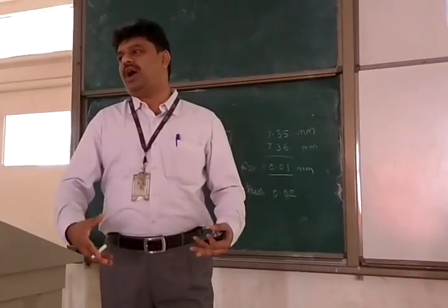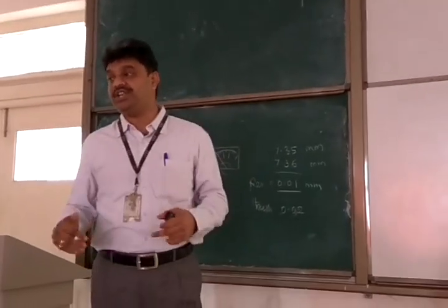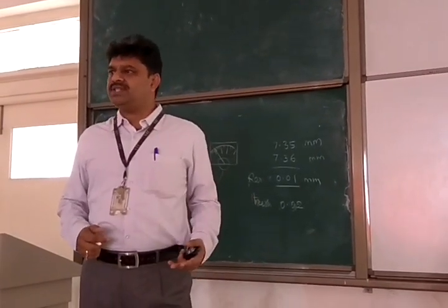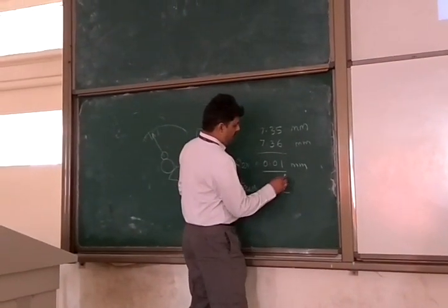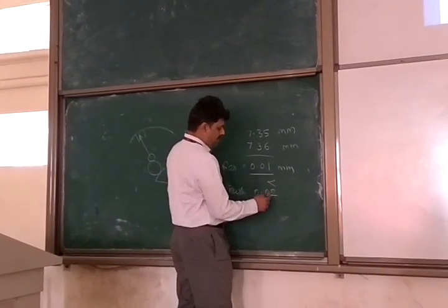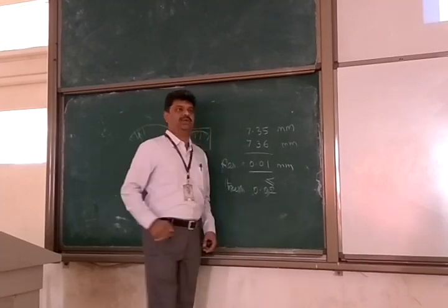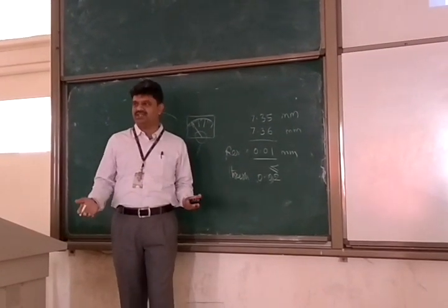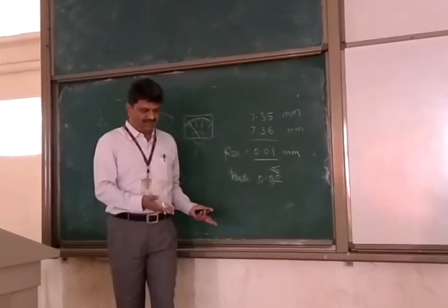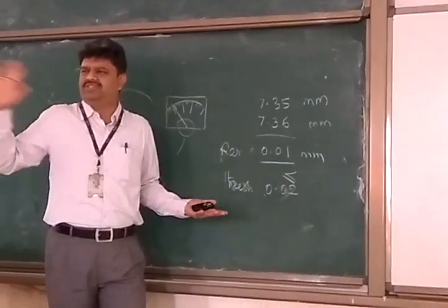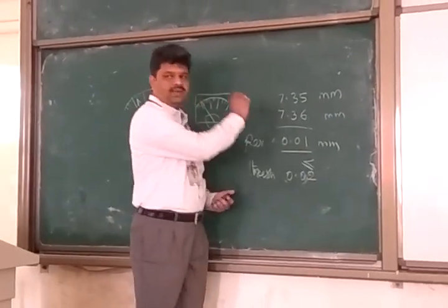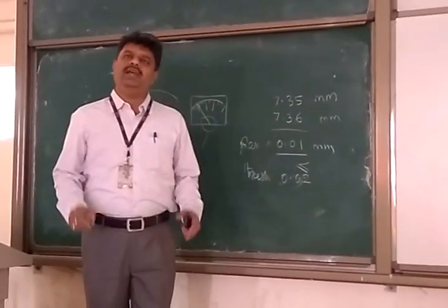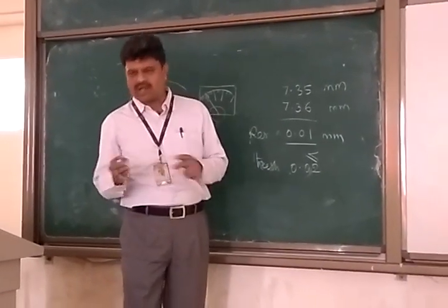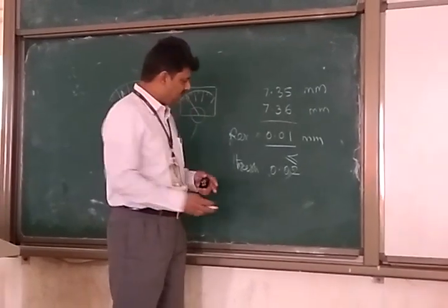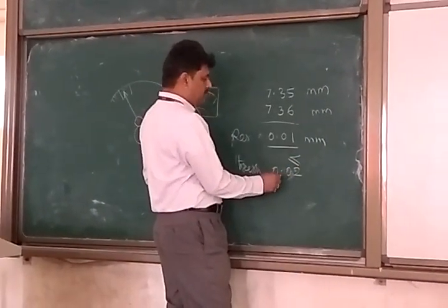You may have to give a little extra to start moving because of the inertia of the system. In digital instruments, your resolution will be less than or equal to your threshold. In today's digital instruments, there is no inertia—whatever present input you give, it shows output immediately in an ideal instrument. So threshold and resolution will be equal. But with electromechanical or pure mechanical devices, inertia is involved, so you will always find threshold is more and resolution is less.